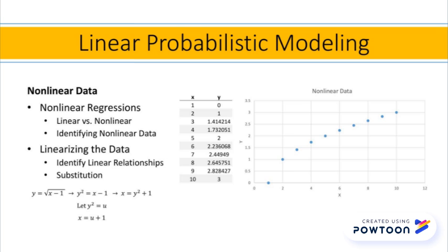The predictive nature of linear probabilistic modeling is essential. Not every value in a sensor's range can be tested. For example, the pressure transducer calibrated here can read far higher and lower pressures than the manometer is capable of creating. Thus, simple interpolation is insufficient. A probabilistic model is necessary to extrapolate beyond the data with a known degree of confidence. When engineers use equipment to test samples or conduct experiments, they should calibrate their equipment via probabilistic model.